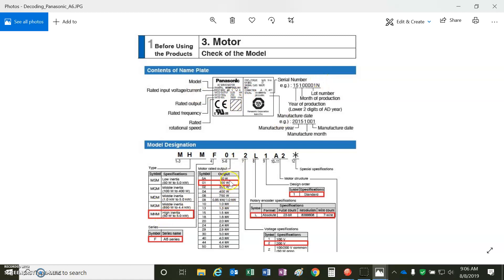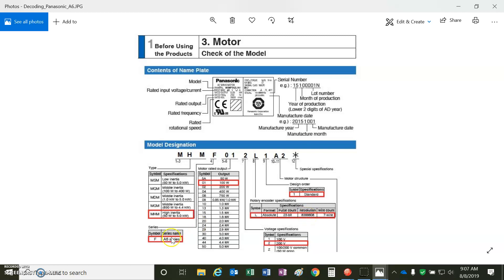We can see this. The little motor is a 100-watt motor. It's rated for 200 volts. It's got the 23-bit absolute encoder, which, of course, is multi-turn, 65536 turns of multi-turn information. And it's the A6 Panasonic motor. So, I was able to get things going just from the tag data.